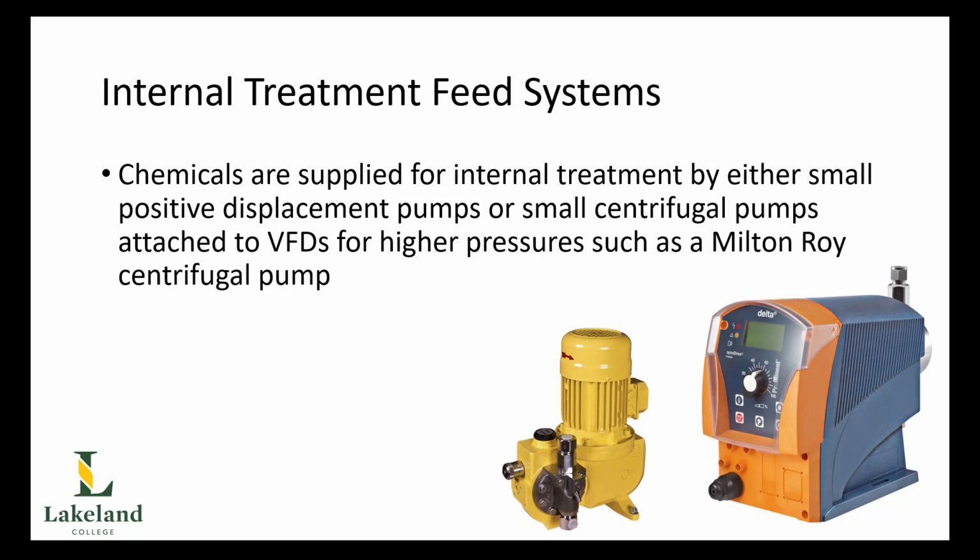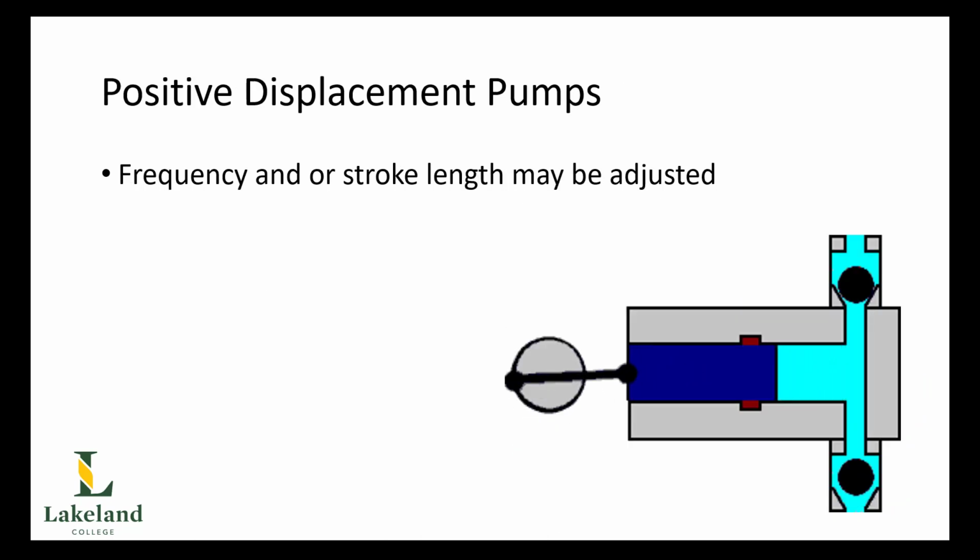water chemistry. Now, the idea here of a plunger pump is that we basically have a pump with 2 check balls in that we're only pulling fluid in on the suction stroke and discharging it on the discharge stroke, and never the twain shall meet. And if you look at the animation, you can see how that works with the placement of the check valves.